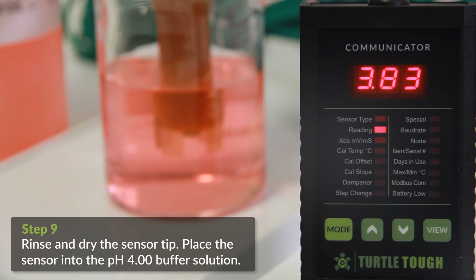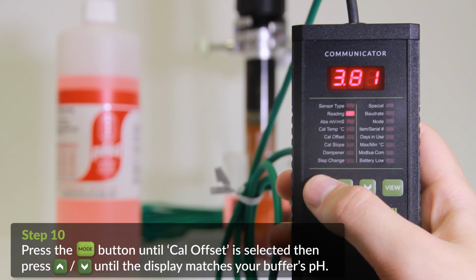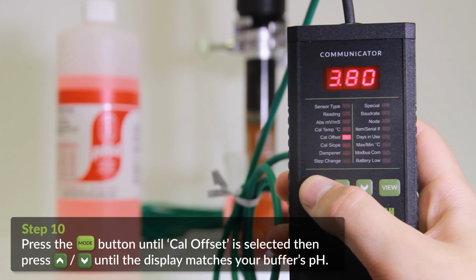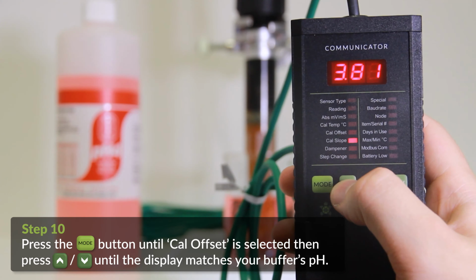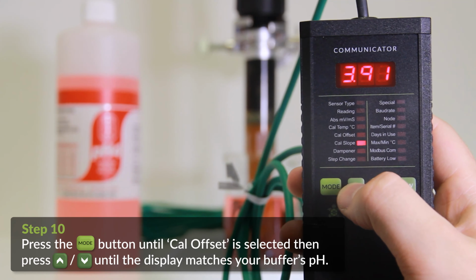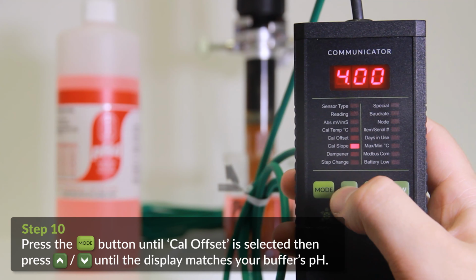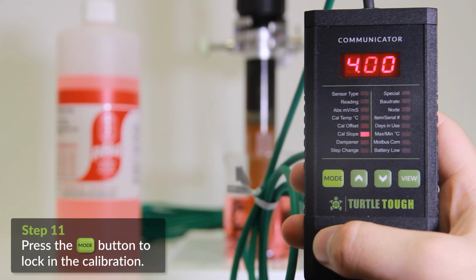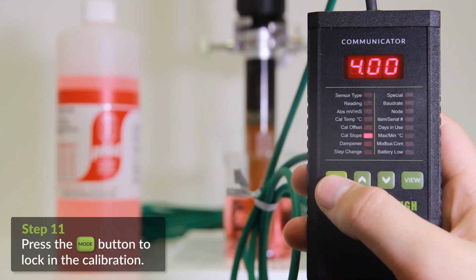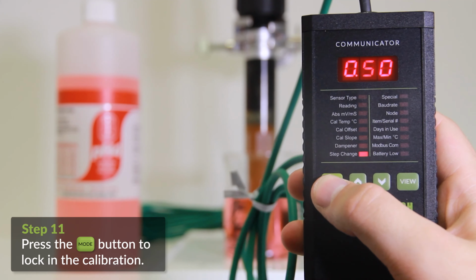Allow a few seconds for the reading on the HFC to stabilize. Press the mode button until the Cal Slope LED turns red. Press the up and down arrow keys until the value on the screen matches the buffer 4 pH value. Press the mode button to save and lock in the offset value and finalize the second calibration.